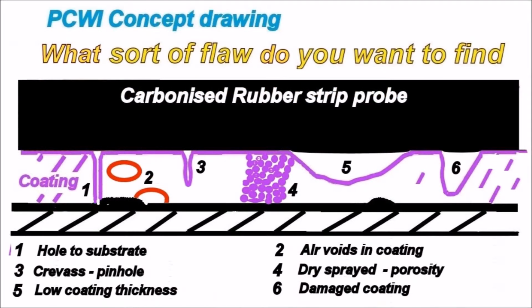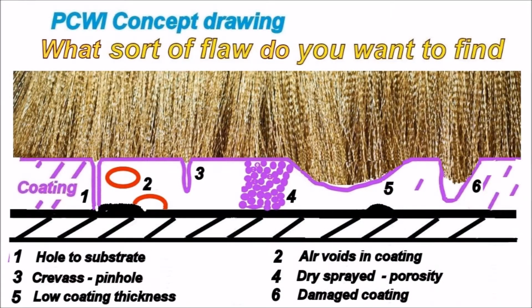If you use a carbonised rubber probe, you're going to find that the gap is increased to the total thickness, but you're not really testing that area with much more voltage. It sort of skips over the top, and if there's any raised sections, it actually lifts up. So it's not a good idea to use these rubber strip probes. The brass wire falls better into the holes, especially when a bit of pressure is put on it. This gives increased searching area.